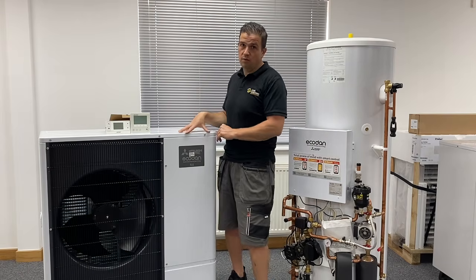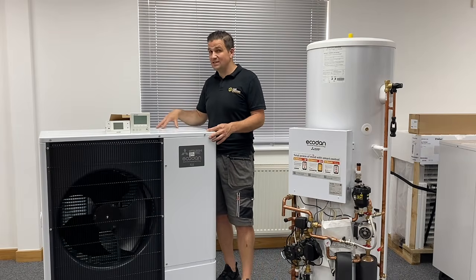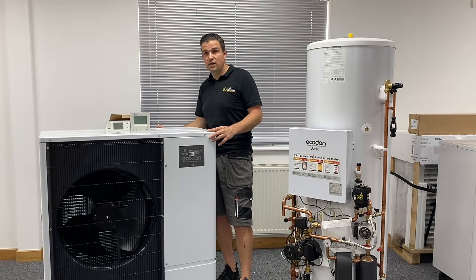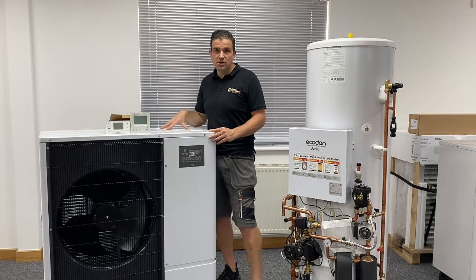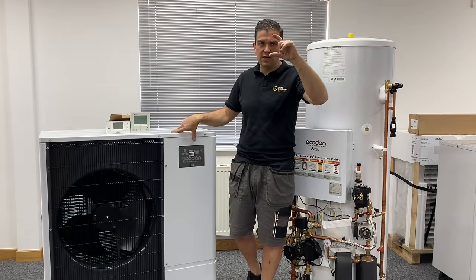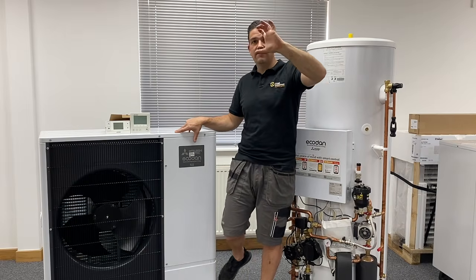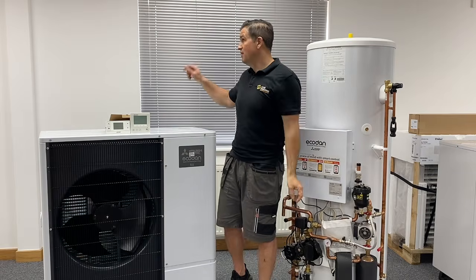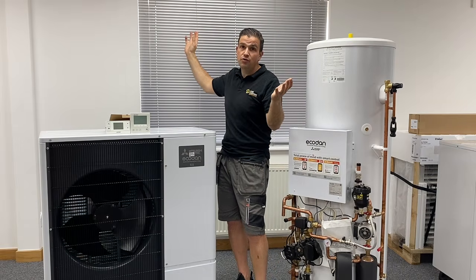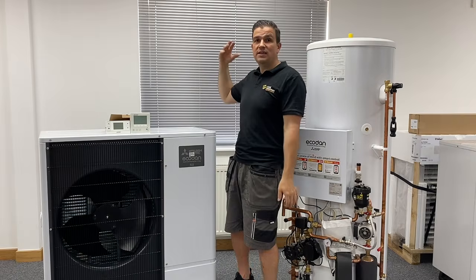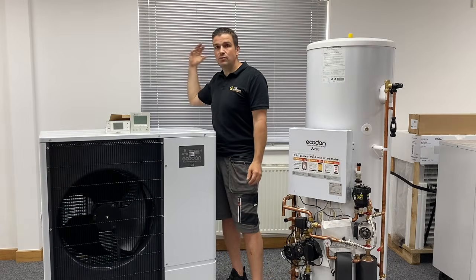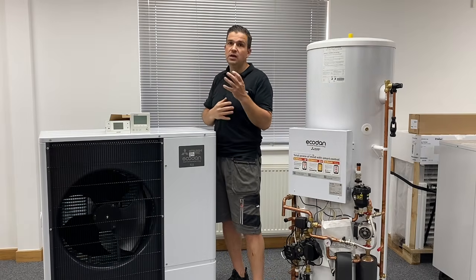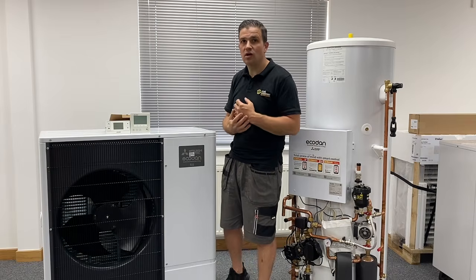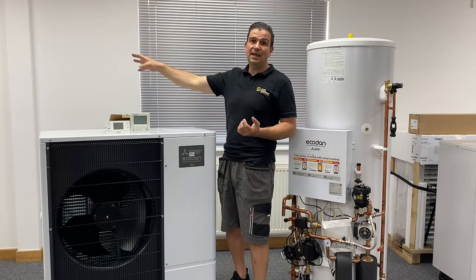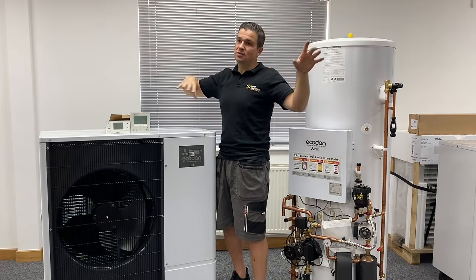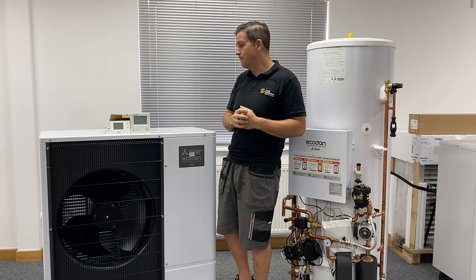These units also come with the outdoor sensor basically attached to the unit. Okay, so with many other installations we would have, and I showed you on the last video, for example, Vaillant or Nibe or whatever, they would have a separate outdoor sensor that you would have to find, preferably on a north facing wall so it doesn't get direct sunlight. And that's giving you a weather compensation, so it's telling you what the temperatures are outside, and it will talk to the heat pump. Does it have to kick in if it's dropping below a certain temperature? How hard is it going to have to work if it's X outside compared to what it's like indoors? It's very, very clever in terms of how it will run.